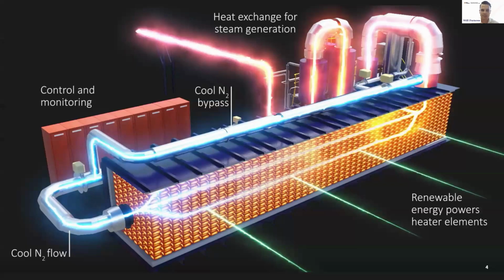Stepping back to the system level: during charging, we use electric resistive heating elements to convert electricity to heat, which we absorb using our MGA blocks inside an insulated enclosure made of mild steel. During discharge, we use a closed cycle nitrogen gas loop to transfer heat from the blocks to an off-the-shelf HRSG, generating high-grade process heat at up to 550 degrees Celsius and well over 70-80 bar pressure.